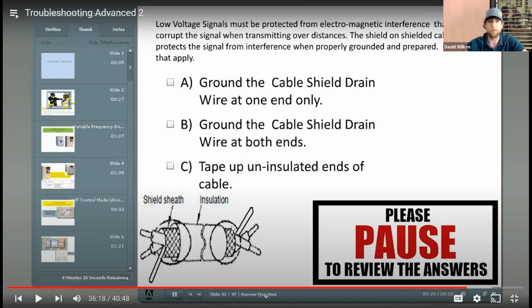So you do want to tape up these shield wires, which are usually bare wires. You'll have several insulated, maybe it's just a pair of insulated wires, and then you'll have one bare shield wire. You ground it on one end, but you want to tape up the other end to make sure that it doesn't accidentally ground. Even though you didn't ground it, you put it to a shield terminal.